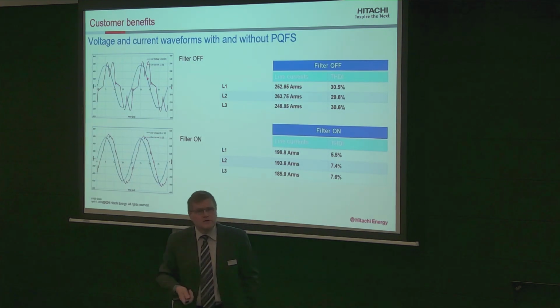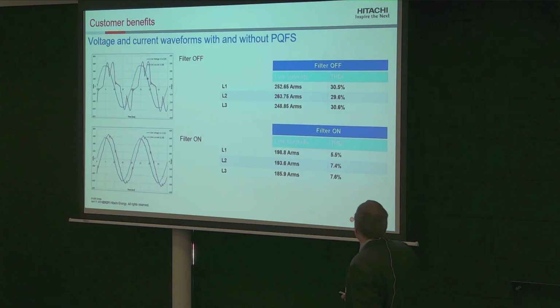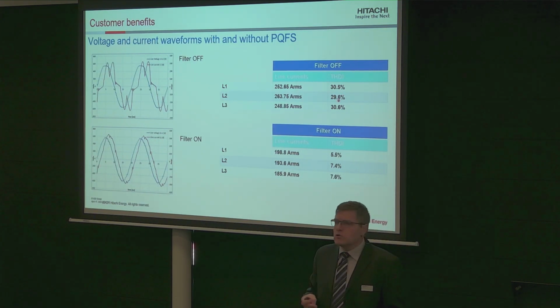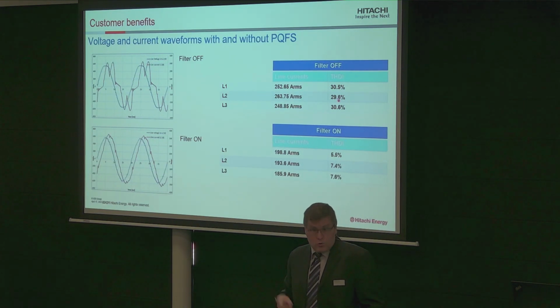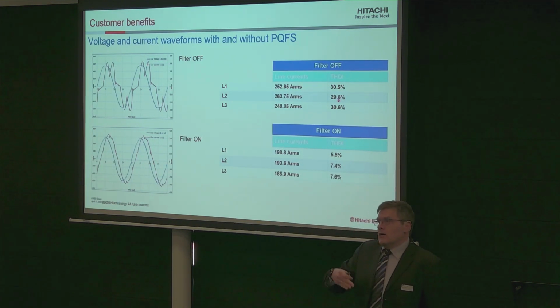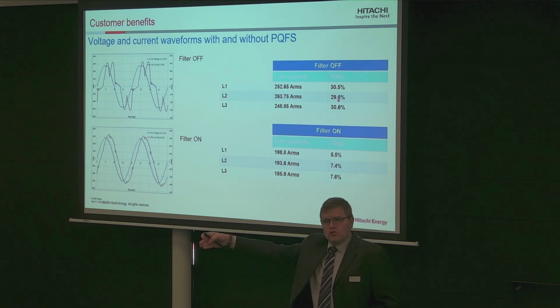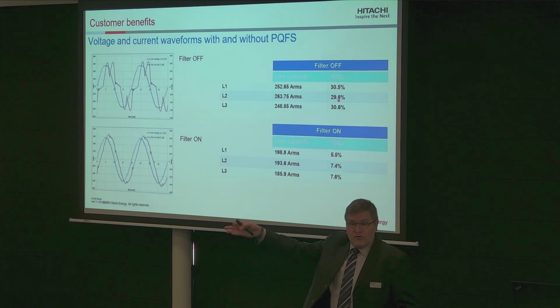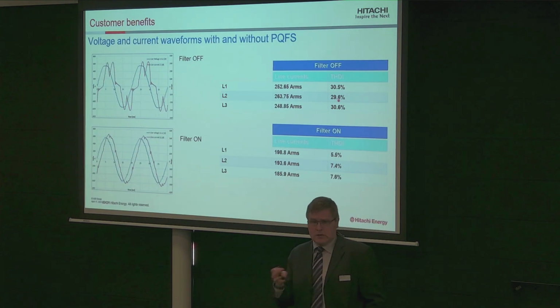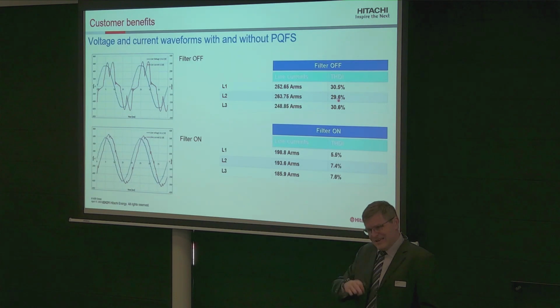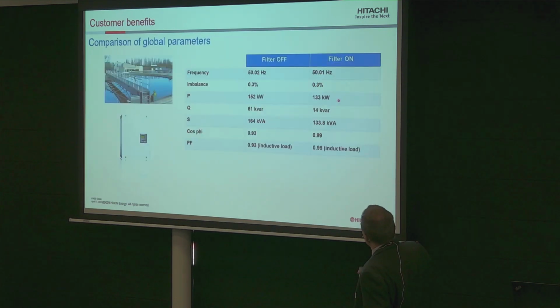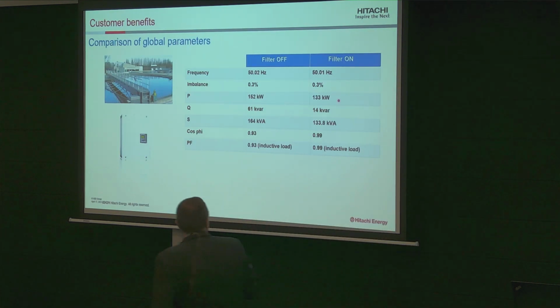harmonic mitigation, compensation, we reduce to a very low level. Here we had a THDI of 30%, and we get down to 5-7%. It was not necessary to go to zero. We can go to zero, but then what is the extra cost to go to zero? Maybe we need to double the number of active filters or add extra equipment. So this is an optimum technico-economical solution.